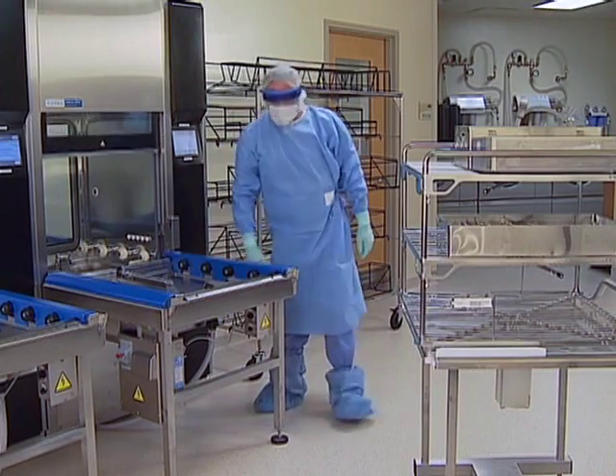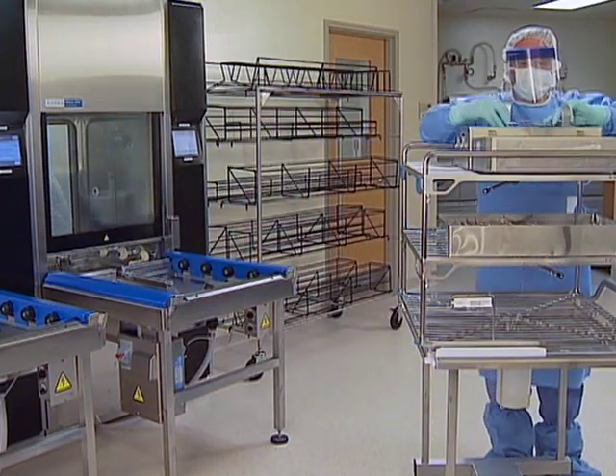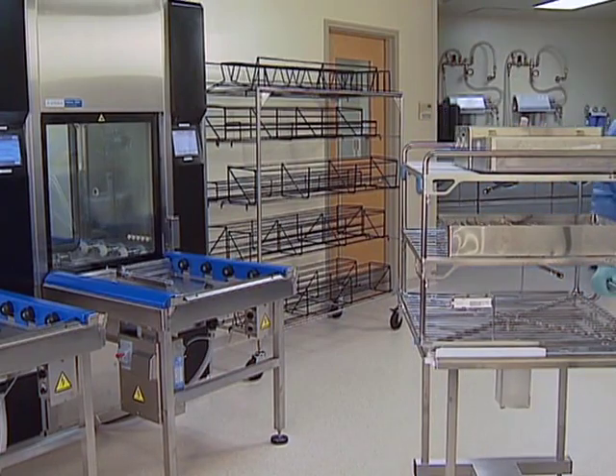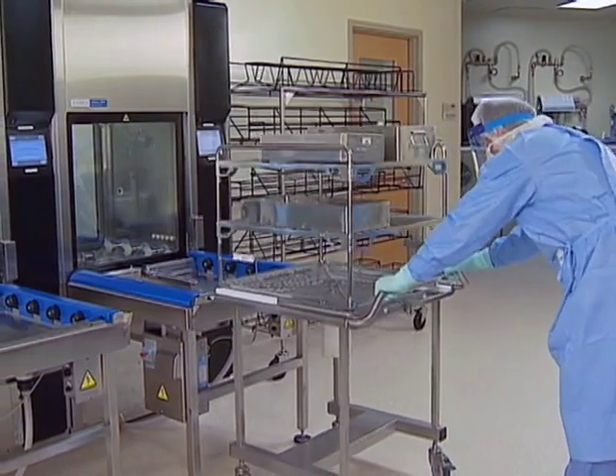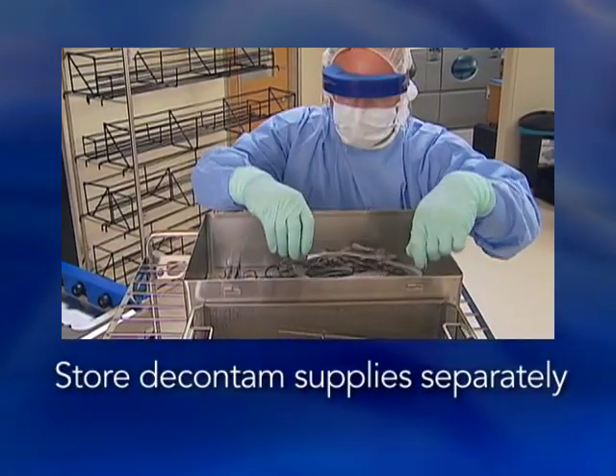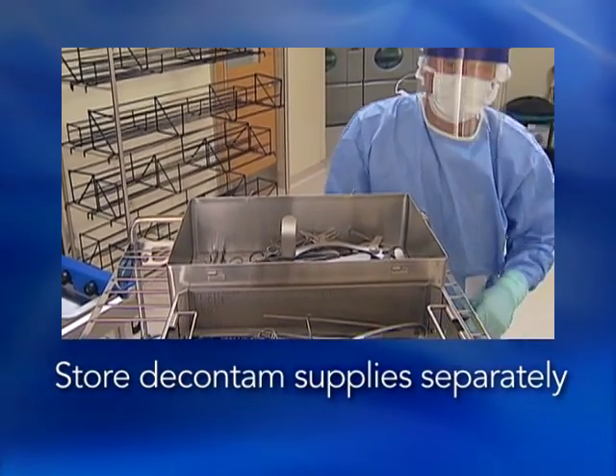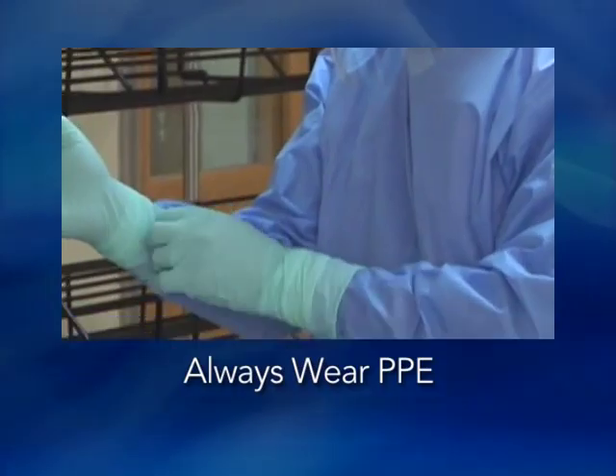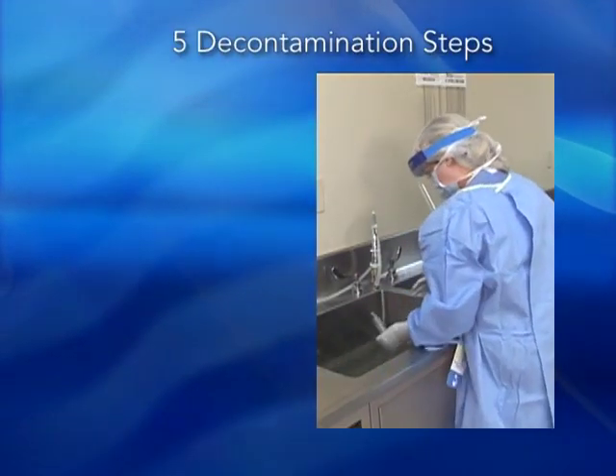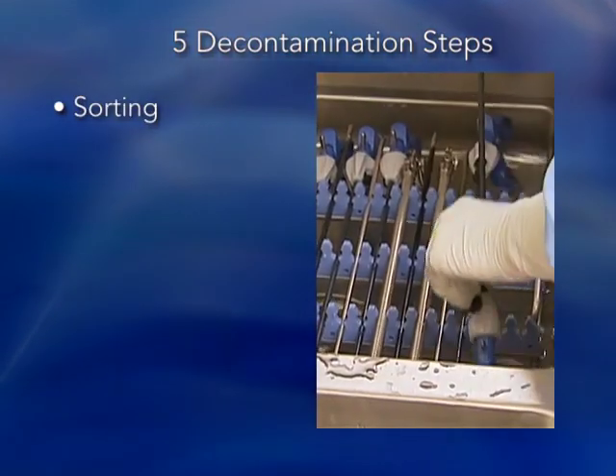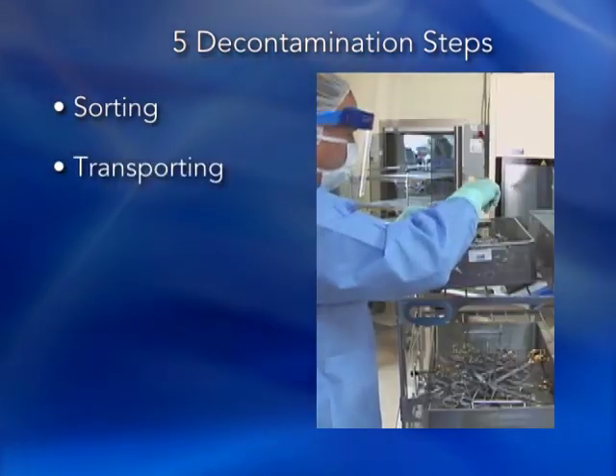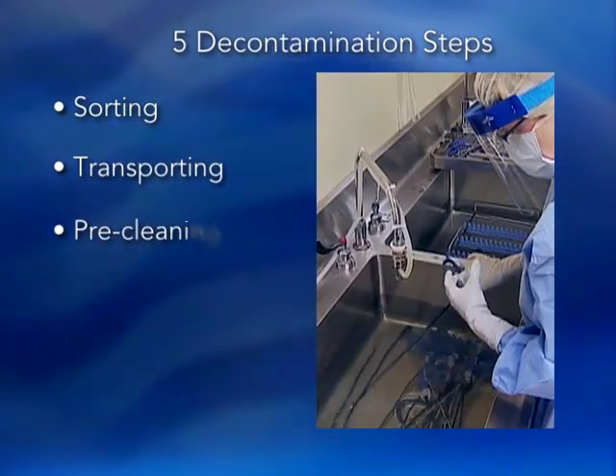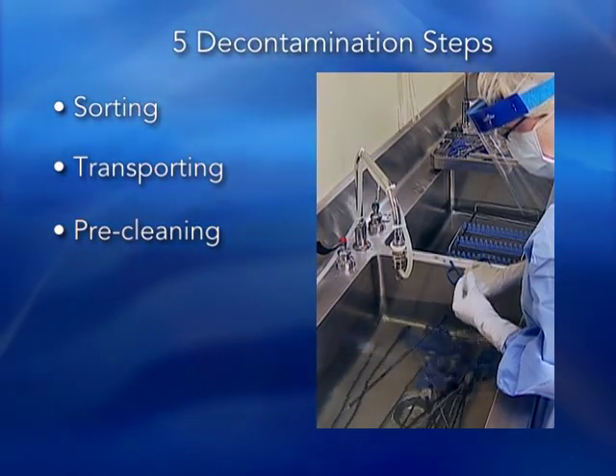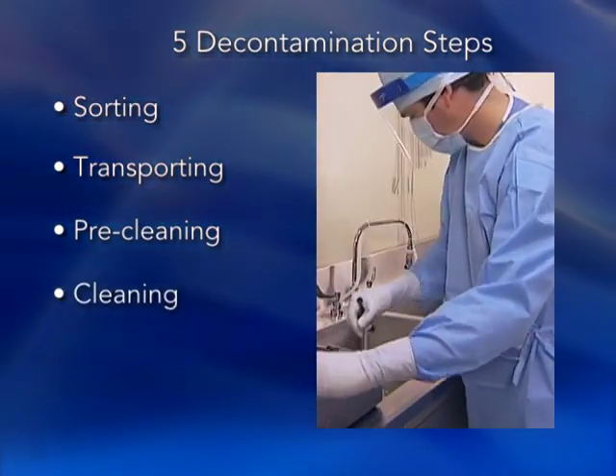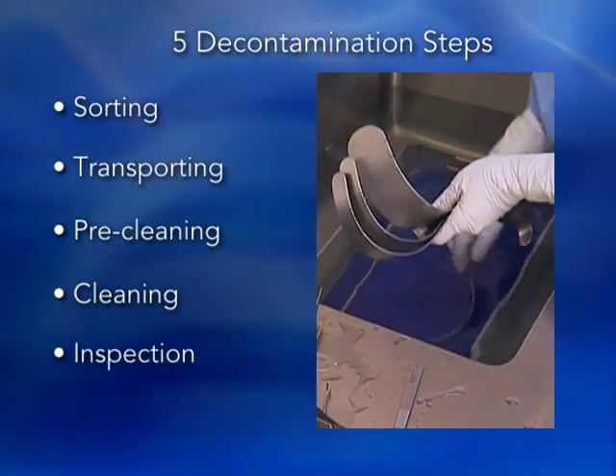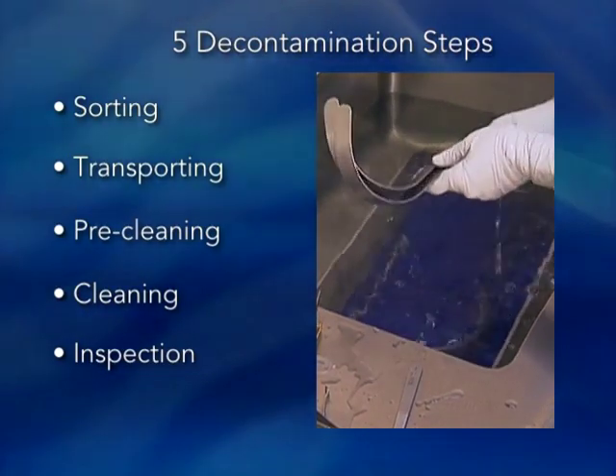The decontamination area, or decontam, is located in your facility's sterile processing department. This area is physically separated from other areas in the SPD to prevent contamination of clean items and work surfaces. Decontam supplies and equipment should be stored separately from the prep and pack areas. Always wear your personal protective equipment when working in this area. Decontamination includes these general steps: sorting instruments and devices after a surgical procedure, transporting them in the appropriate containers to decontam, pre-cleaning, which involves disassembling instruments and devices that have more than one part, manual, mechanical, or sonic cleaning and disinfecting, and inspecting instruments and devices for any signs of rust, stains, corrosion, or damage.